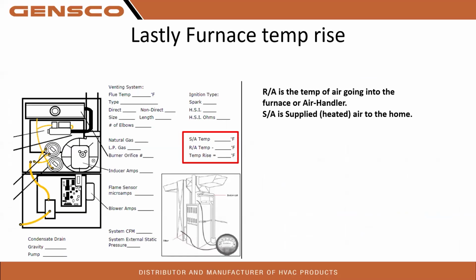Okay, furnace temperature rise, right? So lastly, what we're looking at is what is it doing? What is the return air coming in and what's going out? What is being supplied to the home? What's our temperature difference or temperature rise, right? That can tell us a lot. Okay, we're riding on the high end of that furnace's limit.